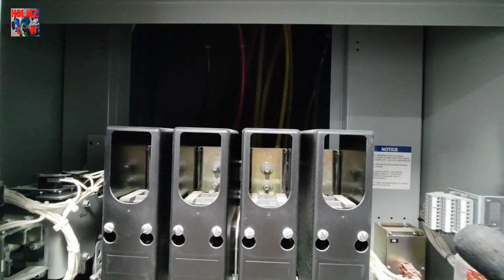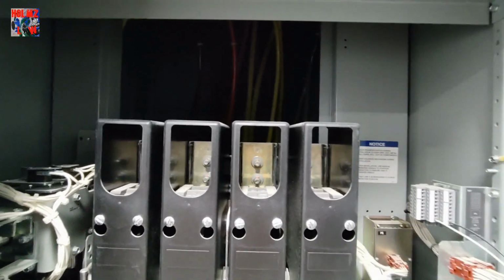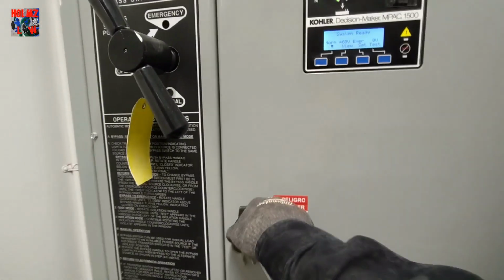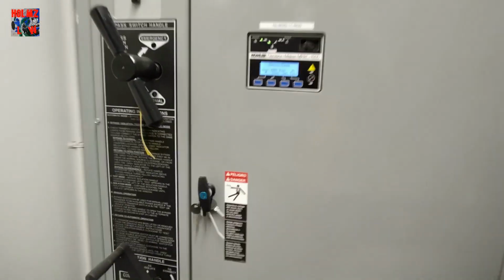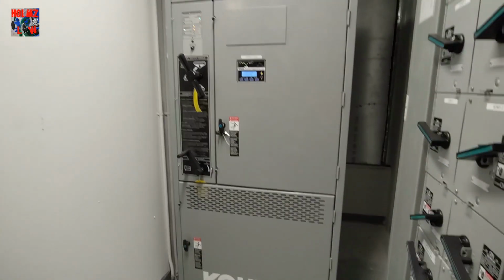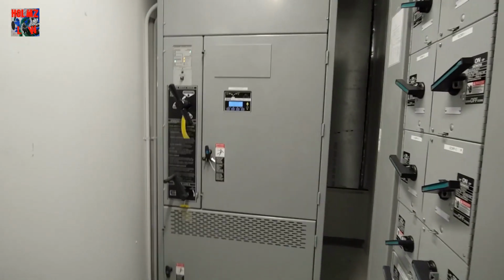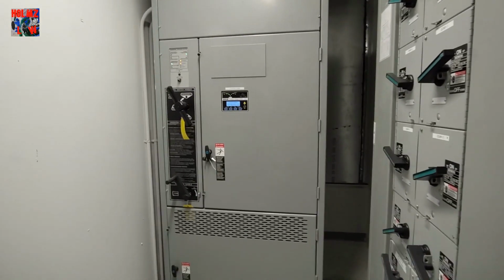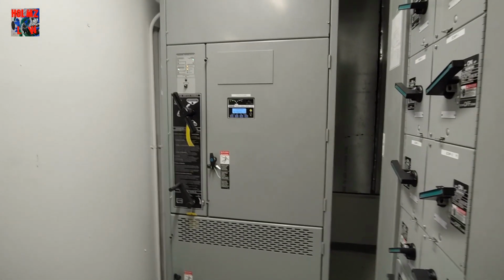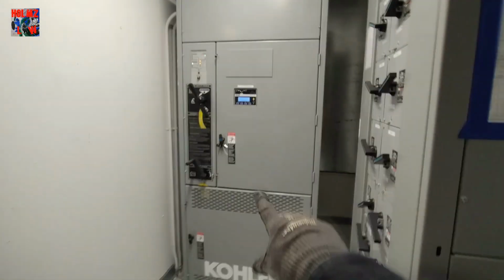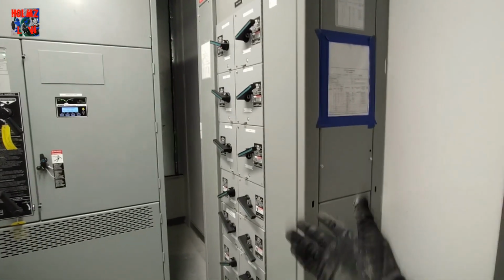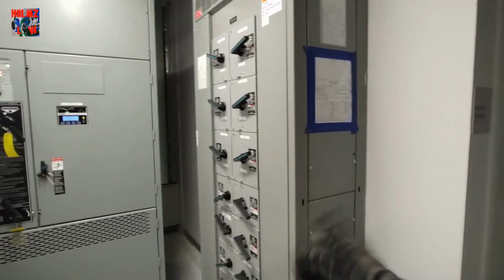Okay. We have, obviously, it's feeding distribution panels, so they have a neutral. Okay. Our other transfer switches do not have any loads that actually are using a neutral. So in that case, we're okay. We don't need to have a four-pole switch because we don't have a neutral in that system anyway. All right. But these loads, being that they are feeding panels, which is this one here, distribution panels, and they're actually coming in with the neutral, then we need to actually switch that neutral. Okay.